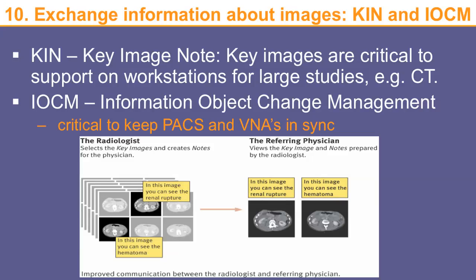Another related profile is IOCM, Information Object Change Management. This is critical anytime we have multiple copies of images — for example, a PACS system sends a copy to the vendor-neutral archive, which may send another copy to an enterprise system. If the PACS administrator finds out there was a major problem with an image — for example, the left-right indicator was wrong or misidentified — and wants to delete or replace it, that information can be encoded in the form of a key object note to delete those images. This allows the correction to be automatically communicated between all the devices.